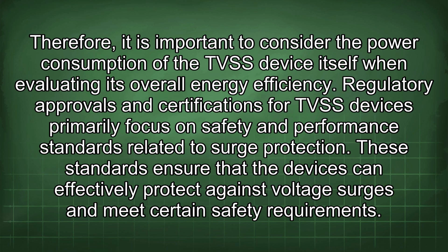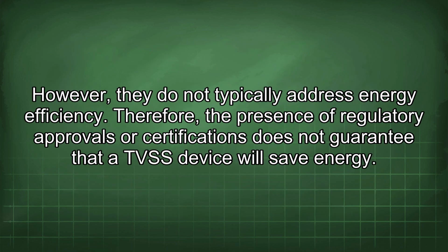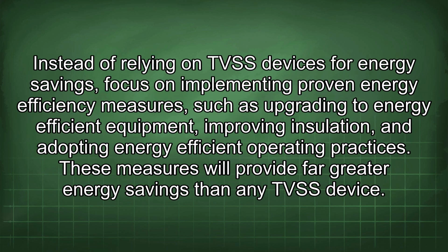Regulatory approvals and certifications for TVSS devices primarily focus on safety and performance standards related to surge protection. These standards ensure that the devices can effectively protect against voltage surges and meet certain safety requirements. However, they do not typically address energy efficiency. Therefore, the presence of regulatory approvals or certifications does not guarantee that a TVSS device will save energy. Instead of relying on TVSS devices for energy savings, focus on implementing proven energy efficiency measures such as upgrading to energy-efficient equipment, improving insulation, and adopting energy-efficient operating practices. These measures will provide far greater energy savings than any TVSS device.